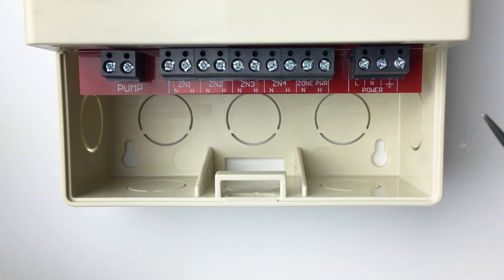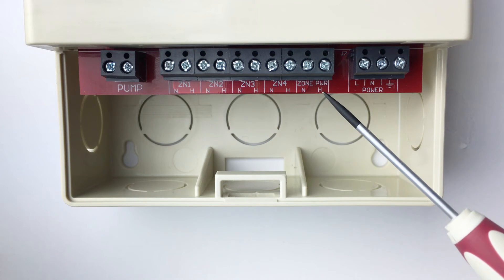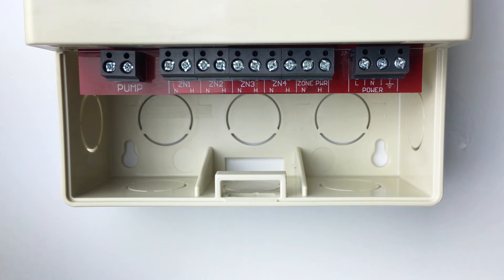Input power: this input is to power the ZON0550. 0.5 amps at 120 volts AC is required to power this device. Zone power: this input is used to power the zone outputs and is rated for 240, 120, or 24 volts AC.